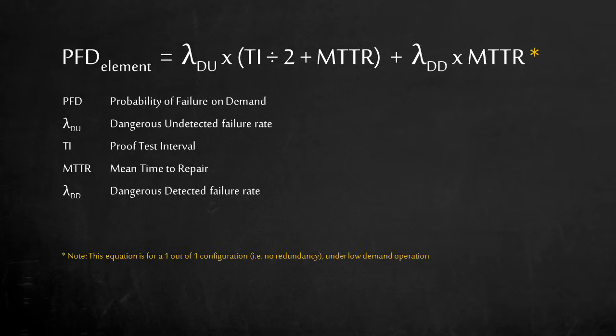This equation only applies to components under low-demand operation with a 1 out of 1 voting logic, which means there is no redundancy. There are other equations for different voting logic, such as 1 out of 2 or 2 out of 3. There are also different equations for safety functions used continuously which is considered to be high-demand operation.